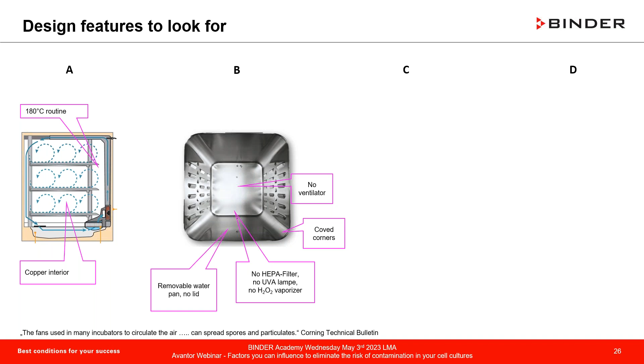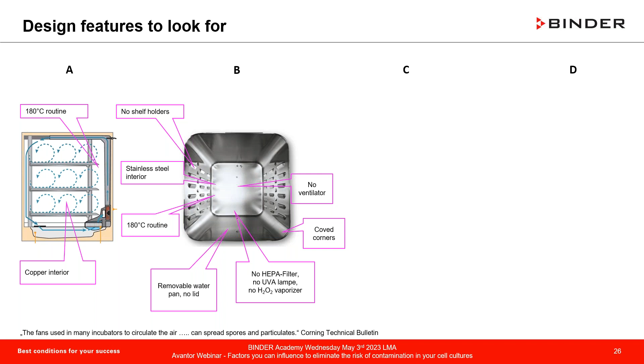You don't have H2O2 vaporization, so occupational health issues are not involved, and recurring costs are also not involved, neither for the HEPA filter, nor for UVA, nor for hydrogen peroxide. We have that water pan inside, naturally, 180 degrees C routine, the gold standard today, stainless steel, no shelf holders. We don't have a rack like A does, so there's no disassembly and assembly time wasted. You can immediately then start up at 37 degrees C in incubation, no air duct system.